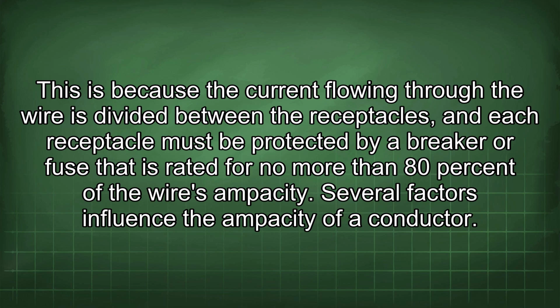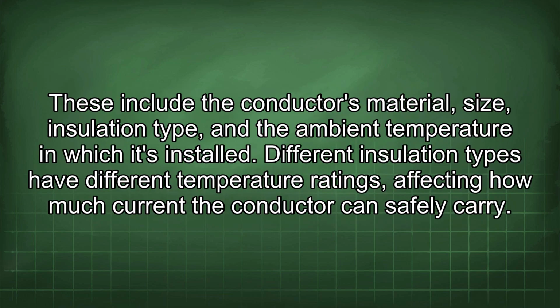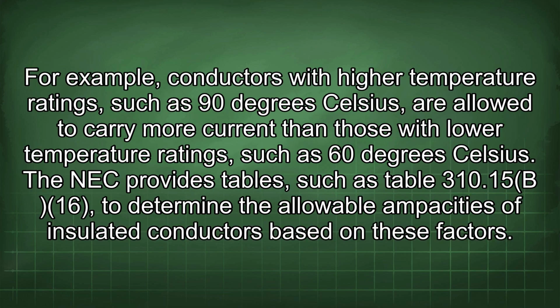ampacity. Several factors influence the ampacity of a conductor. These include the conductor's material, size, insulation type, and the ambient temperature in which it's installed. Different insulation types have different temperature ratings affecting how much current the conductor can safely carry. For example, conductors with higher temperature ratings, such as 90 degrees Celsius, are allowed to carry more current than those with lower temperature ratings, such as 60 degrees Celsius.